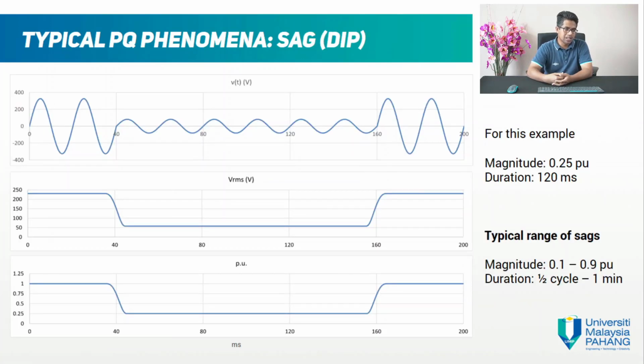Okay, sag. This is the most discussed power quality problem. Okay, because sag happens every day, and it constitutes maybe 70 to 80% of power quality problems worldwide. Another name for sag is voltage dip or power dip. Okay, how does it look like? We want voltage like this. Okay, I'll show you. Okay, this is what we want. Okay, this is an example for single phase.